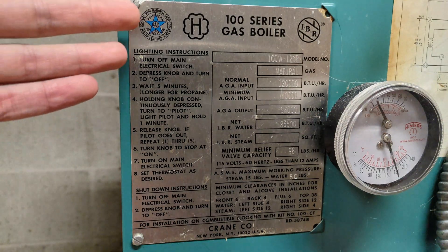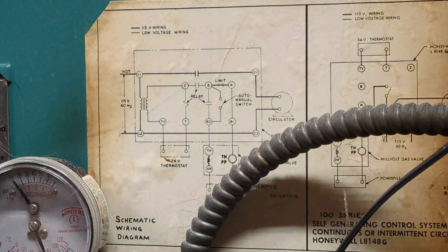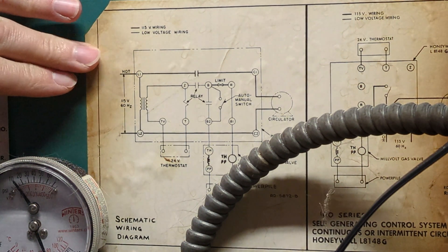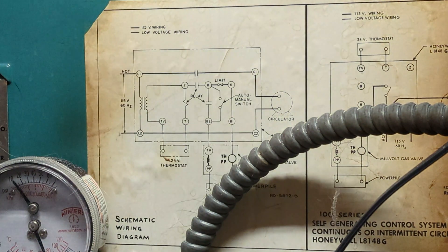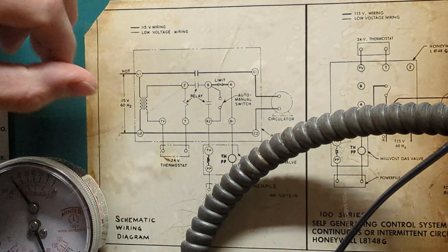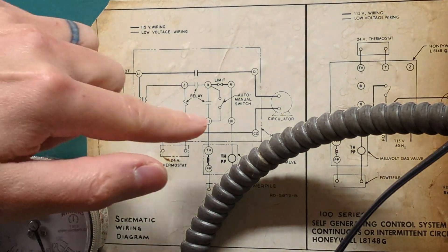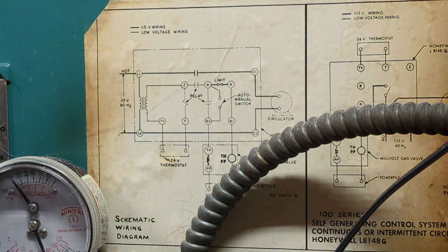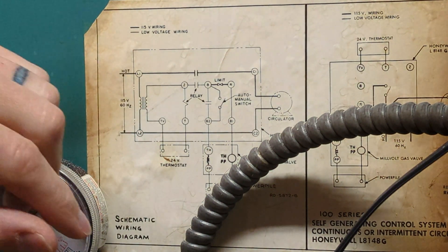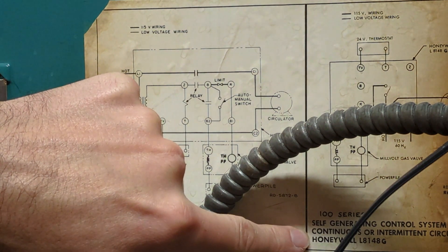The specific boiler I have is the 100 Series gas boiler — it's made by Crane and has Honeywell controls. I don't have the manual since this is from the 1970s, but thankfully there's a nice wiring diagram schematic here. The line voltage powers the circulator pumps, and when the thermostat calls for heat it trips this relay, which tells the burner to turn on. Right here you can see it says Auto/Manual Switch — that's part of what we're going to work on to get this running in continuous circulation mode.